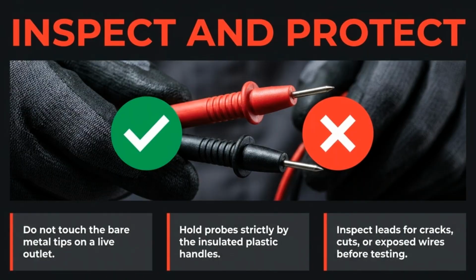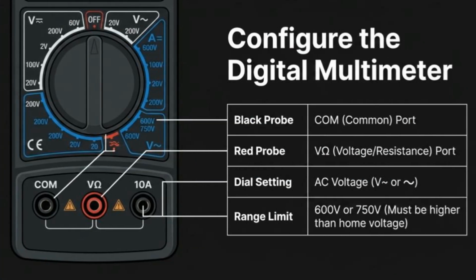Hold probes strictly by the insulated handles, and never touch the bare metal tips on a live outlet. To configure the multimeter, connect the black probe to the COM port and the red probe to the V-omega port. Set the dial to AC voltage and choose a range limit of 600 volts or 750 volts.